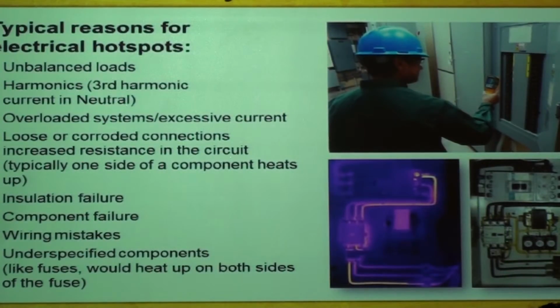Loose or corroded connections. If the connections are loose, corrosion, rusting is eating away the connections, you are changing contact resistance. If contact resistance changes, the power will change. And that's why an instrument like insulation testing is a part of predictive maintenance, because people measure insulation of cables, but also things like low resistance ohm meters are used to measure the contact resistance as well. Insulation failure. PVC cabling, if the insulation is failing, you've got problems there. Wiring mistakes, component failures, and of course you have under-specified components like fuses.